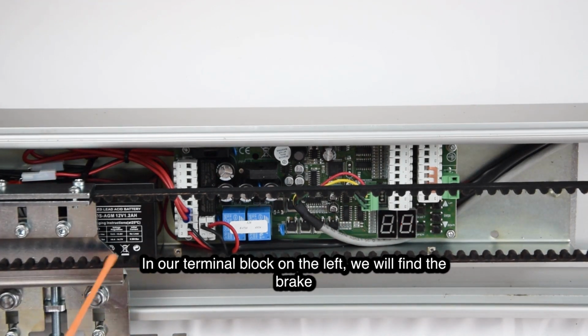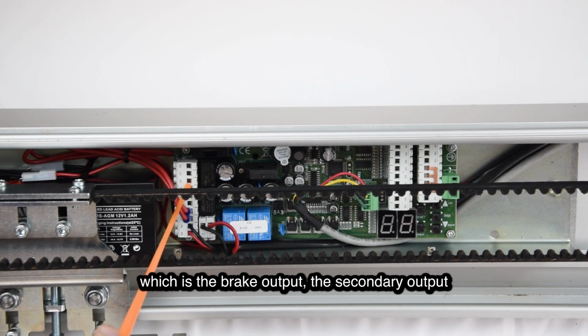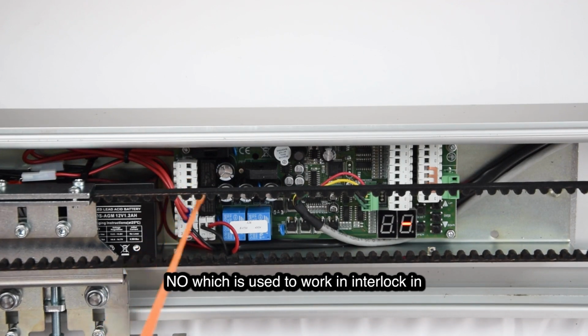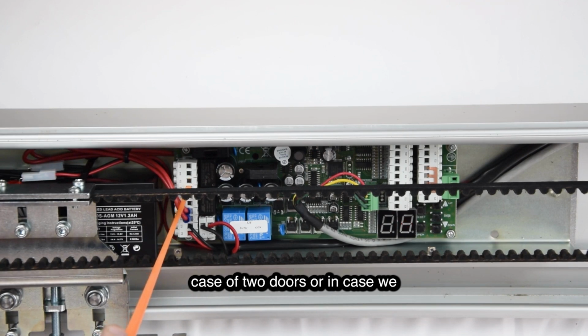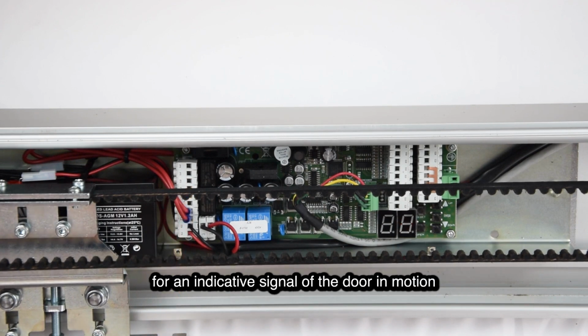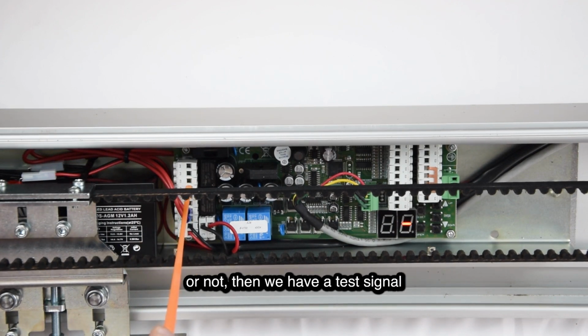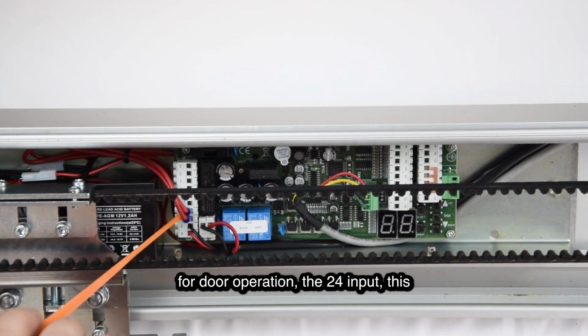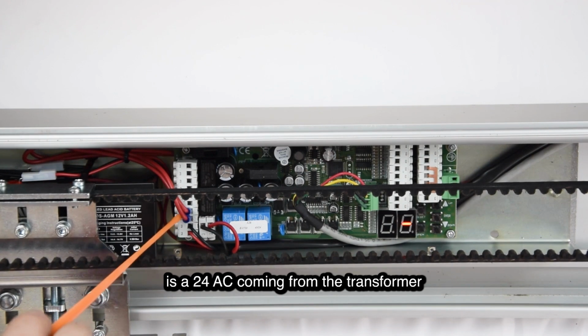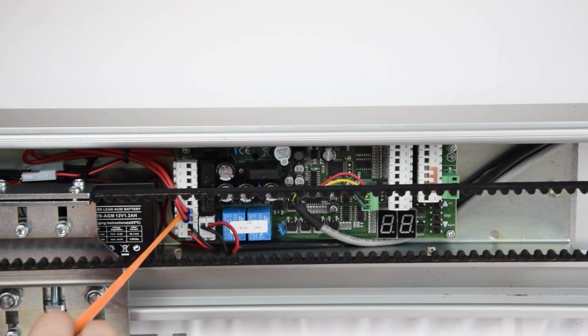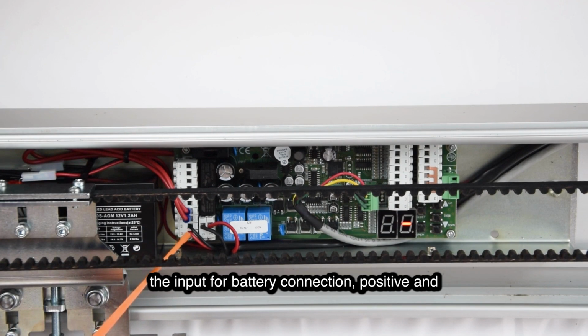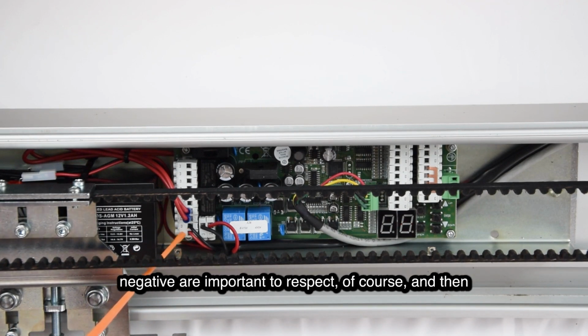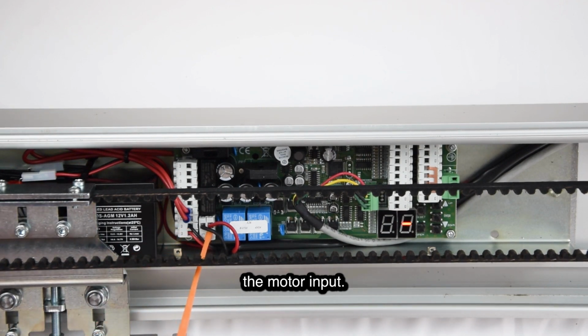In our terminal block on the left, we will find the brake output, the secondary output, NO, which is used to work in interlock in case of 2 doors, or in case we need a NO or NC contact for an indicative signal of the door in motion or not. Then we have a test signal. For door operation, the 24 input, this is a 24 AC coming from the transformer. The input for battery connection, positive and negative, are important to respect, of course, and then the motor input.